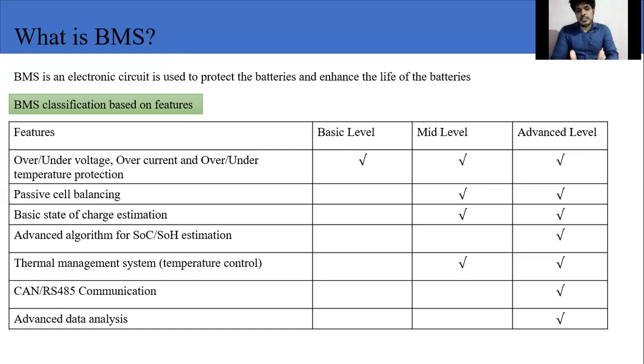According to the under voltage protection, if one battery reaches its minimum voltage level, it will disconnect the discharger. So we cannot discharge the other two batteries to their minimum voltage level, because now the discharge is almost stopped. Then if you charge the battery cells again, the voltage gap between the battery cells will increase. Likewise, this battery voltage gap will multiply and increase over time, so we cannot use the full capacity of the battery because of that.